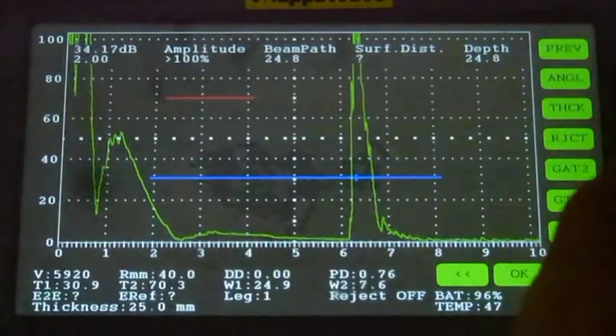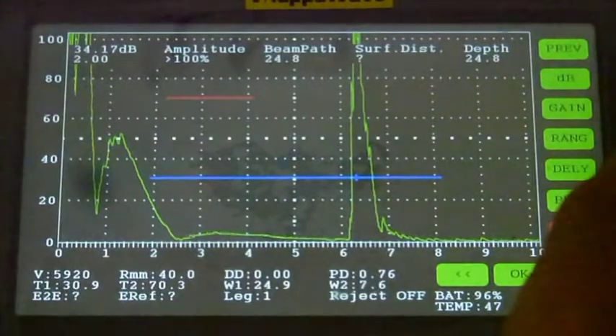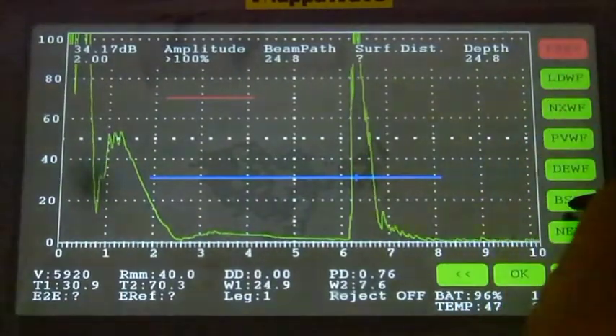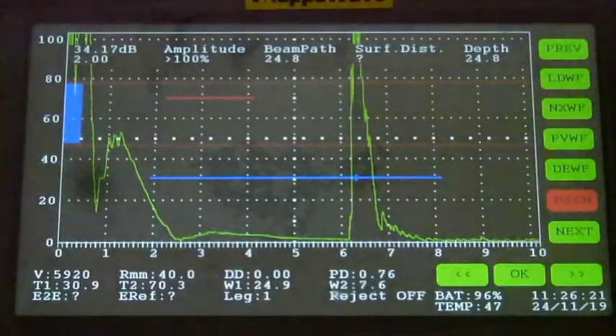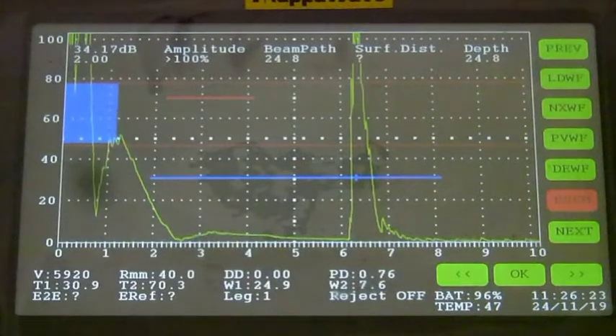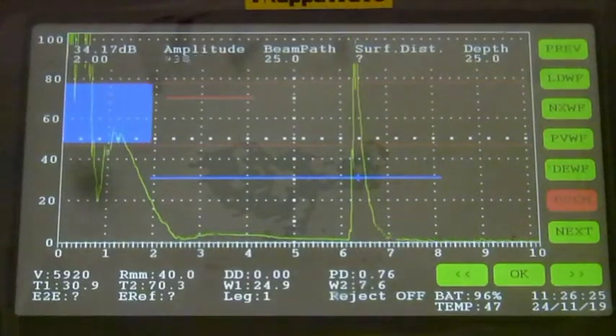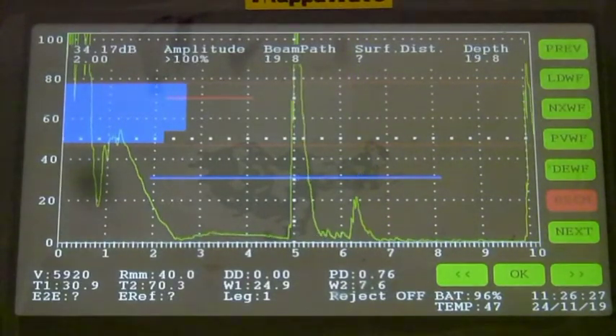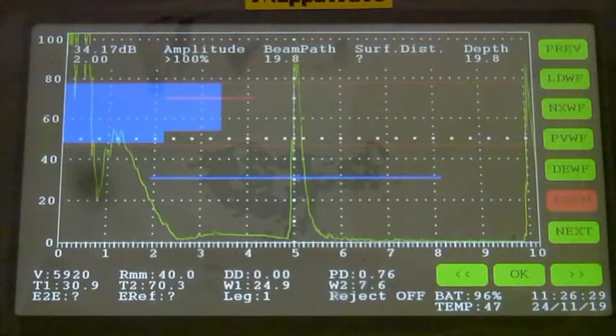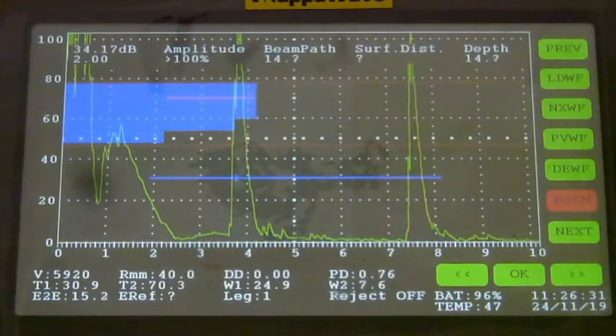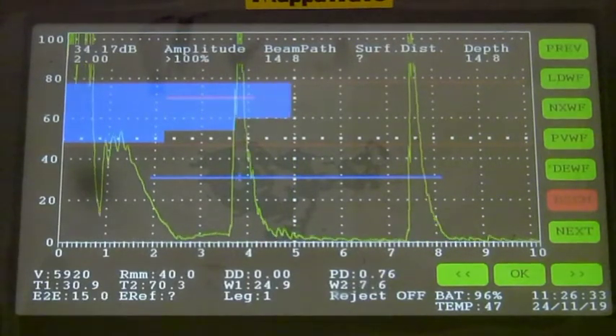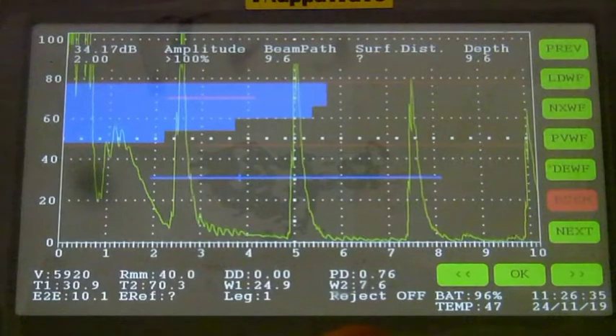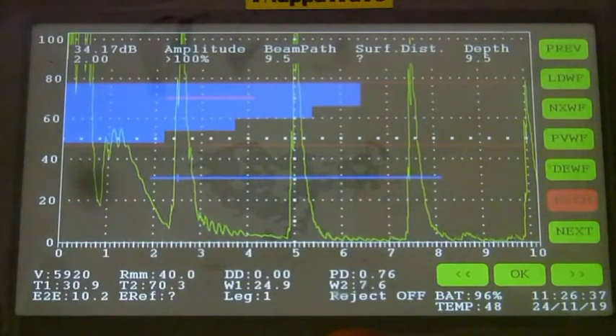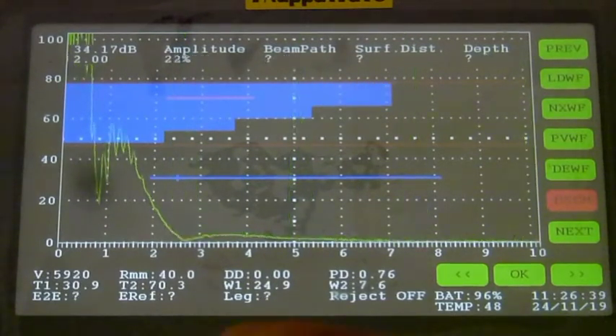Another feature of this instrument is B-scan. It gives you a cross-sectional plot. I'm trying to test a step block of 25 millimeter thickness, so the value of 25 millimeter is entered into the instrument. And as I scan, 20 and then 15 and 10 millimeter thickness can be easily monitored. This gives you a cross-sectional plot. It becomes quite usable in the case of corrosion monitoring and all.